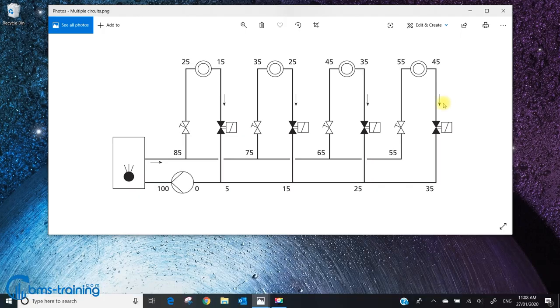So in around 2005, when I first started working this out, I started to try and add some extra resistance to my valve authority formula. But the problem is that we don't know what the local circuit pressure is, 15, 20, 30 meters away from the plant room, down two floors, loads of pipe bends, all sorts of other AHUs. We don't know that. So I started saying, look, I'm going to divide my 10 kPa by 10 plus 10, plus I used to allow 7 kPa for the commissioning set, and I used to allow 3 kPa for pipe bends.